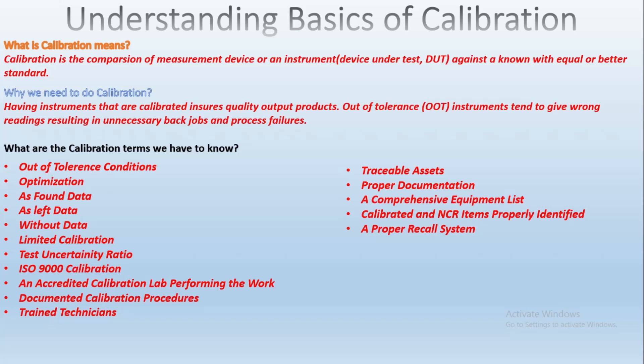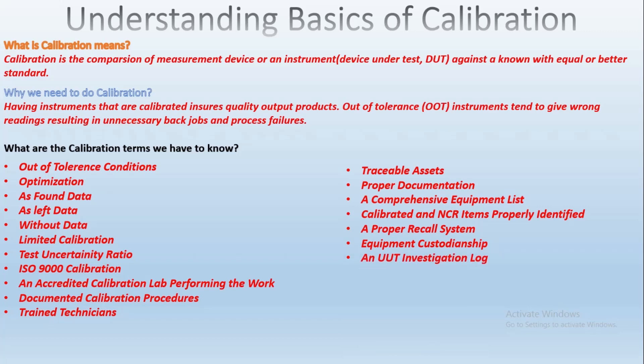A proper recall system should be established with time frames for recall notification, an escalation procedure, and provisions for due date extension. Equipment custodianship — responsibilities for ensuring the equipment is returned to the calibration lab — should be assigned and delegated. Finally, an OOT investigation log: any instrument found out of tolerance requires an investigation to determine the impact on manufacturing records, and reports need to be maintained.